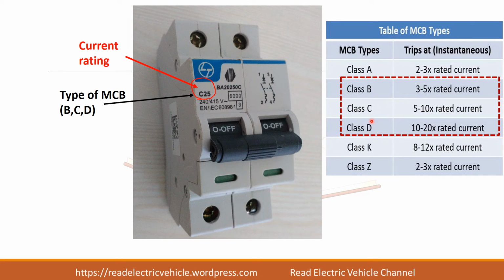So if you want details about this, you can see the previous video on house wiring which I have given in this Read Electric Vehicle channel. So now this C represents that this MCB belongs to class C. That is, it will trip when the current is between 5 to 10 times the rated current. So what is the rated current? 25 amps is the current rating of this MCB.